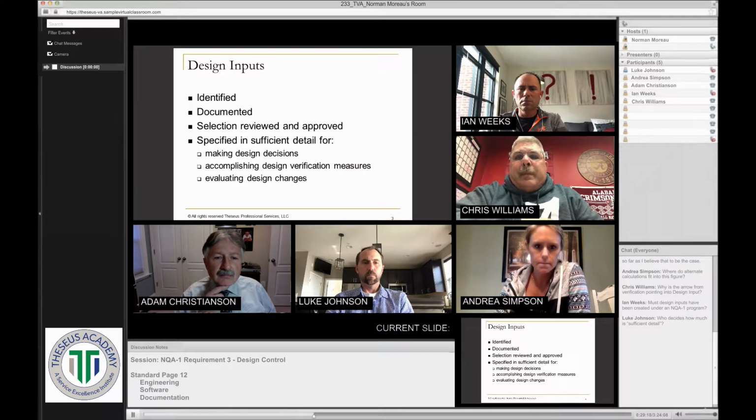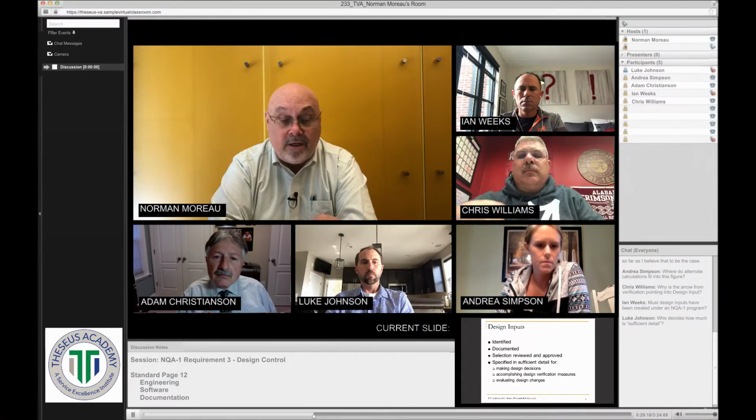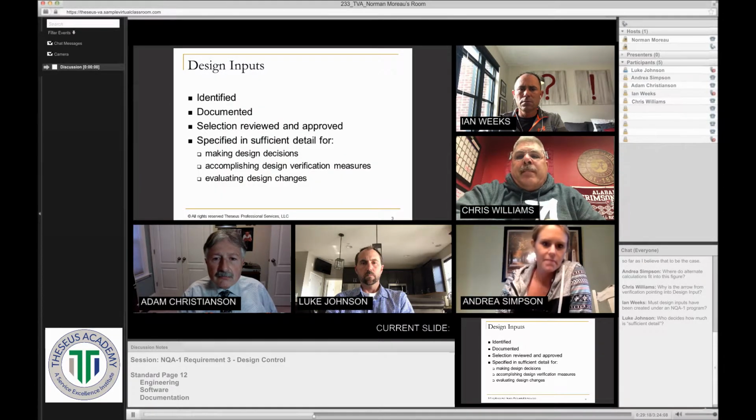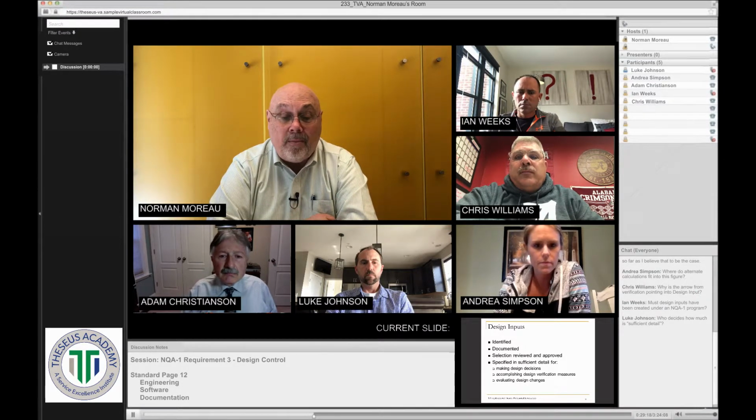specified in sufficient detail. So you've got to have enough information so you can make a decision about the design, that somebody can actually do a verification, because everything we do has to be verified, and it has to be done by somebody who didn't do the work. And then the last item is it's used in evaluating design changes. 5-10 years down the road, some of these plants are running 40 years. I've got to know what you did as far as making your decision.